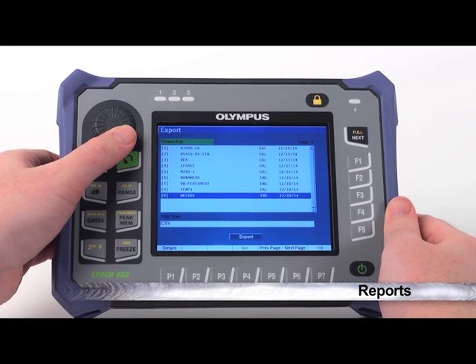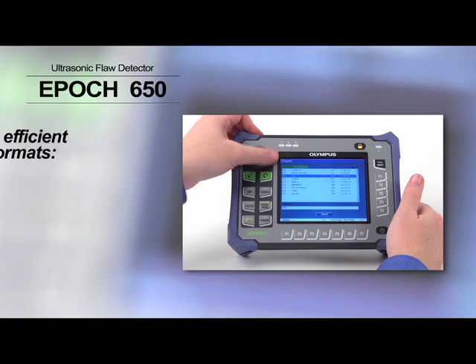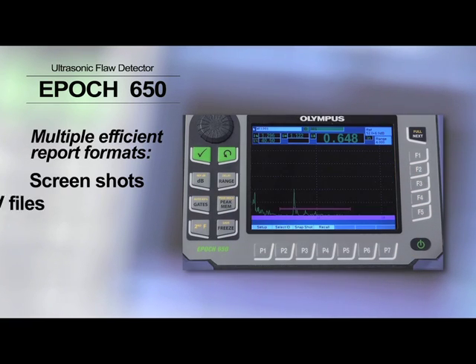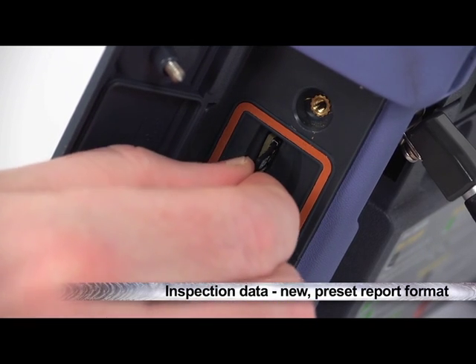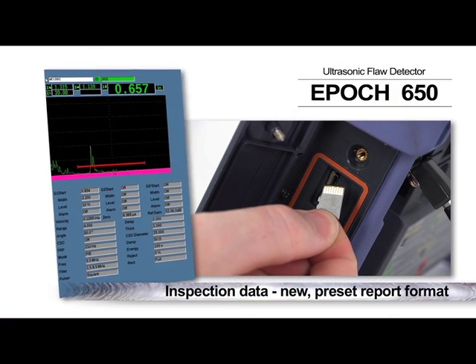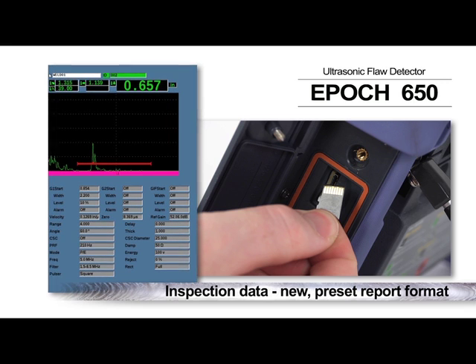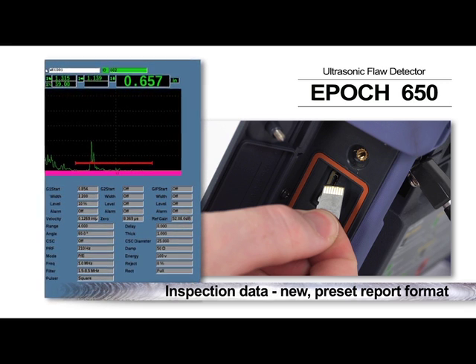After obtaining fast and reliable inspection results, providing a final report has never been easier than with the EPOCH 650. Multiple efficient report formats and outputs are available, including screenshots, CSV files, and XML files. Inspection data can also be sent directly to the MicroSD card in a new preset report format. Each report is saved on removable memory as a bitmap picture file, allowing you to include EPOCH 650 inspection data in virtually any computer report.